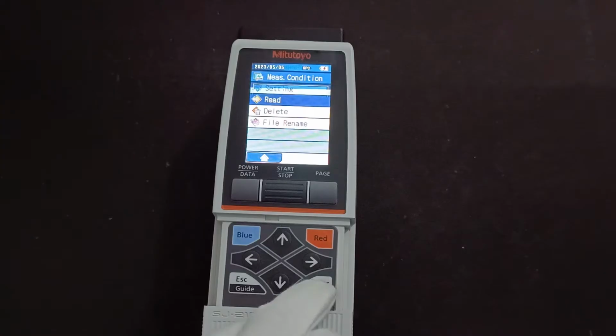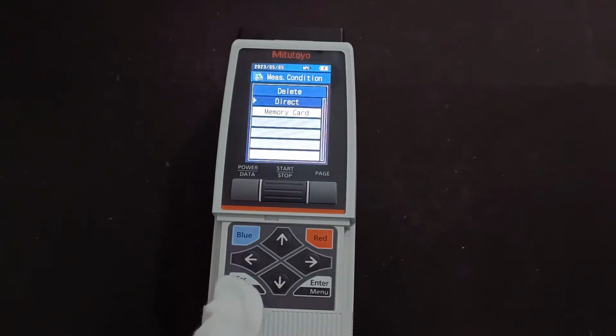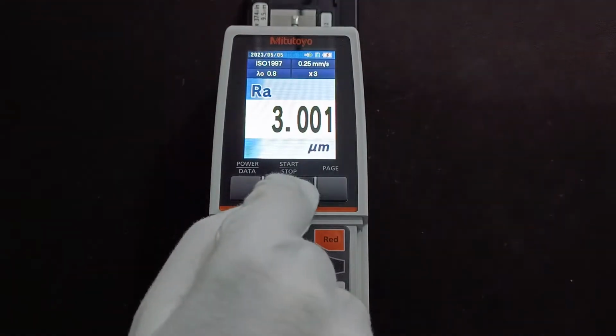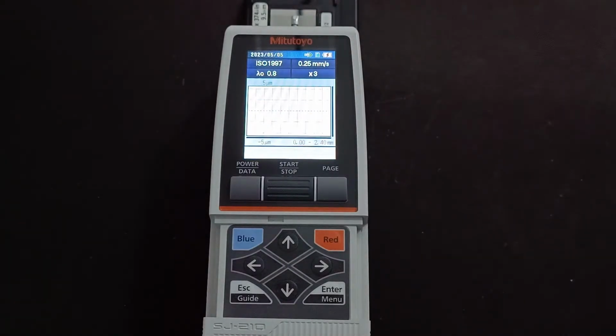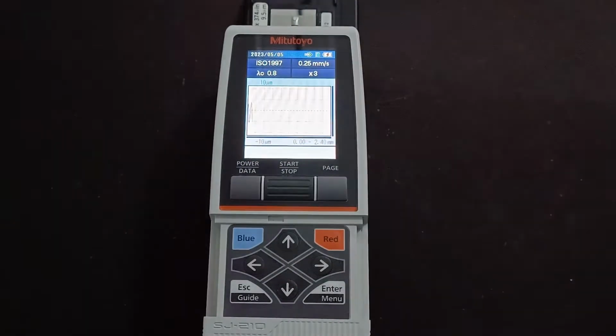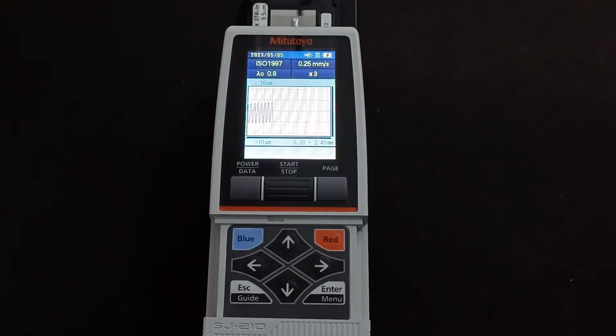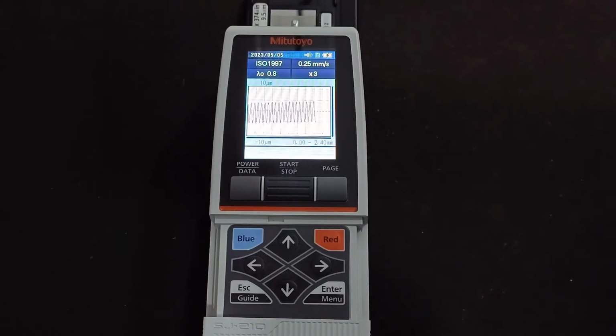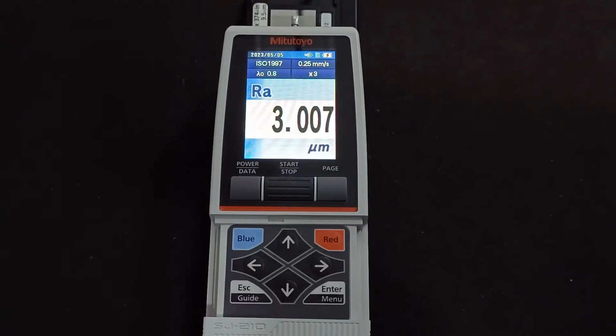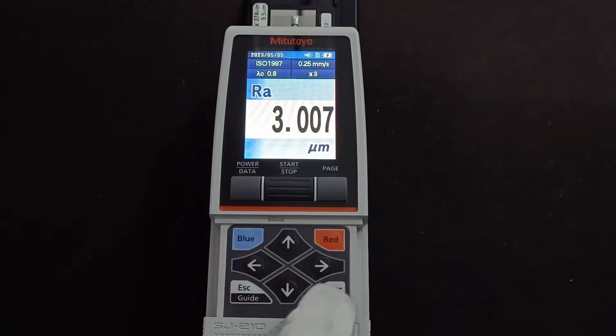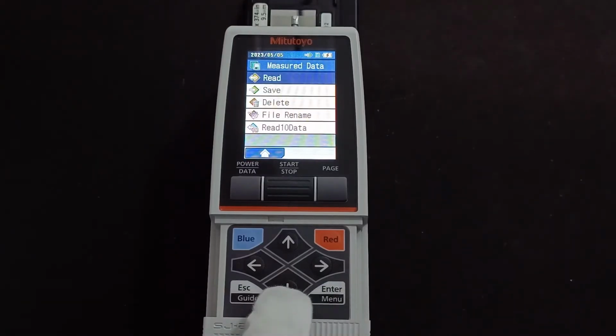The other options in measure condition are read, delete, and file rename. This can be done in internal storage as well as in the memory card. Measured values can be accessed only through a memory card. Files can be read, saved, deleted, renamed, and the last 10 readings can be viewed. Let's see how to use these options. Let's measure a value. Our measured Ra value is 3.007 micrometer. Let's save this reading.